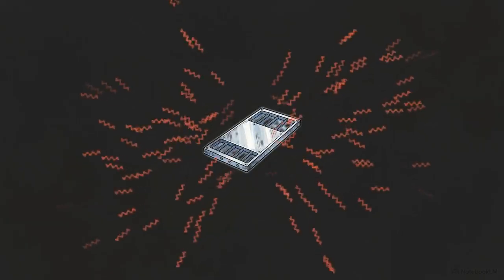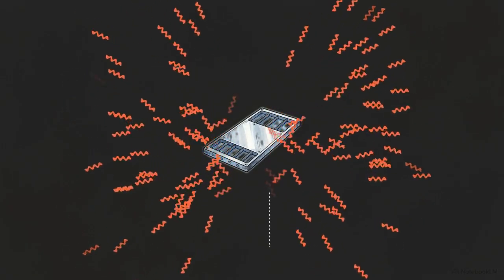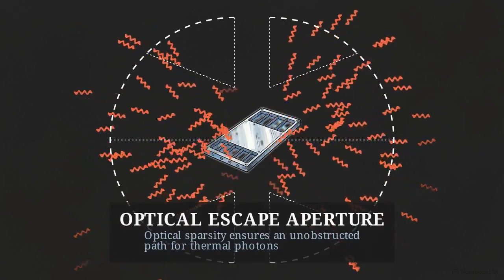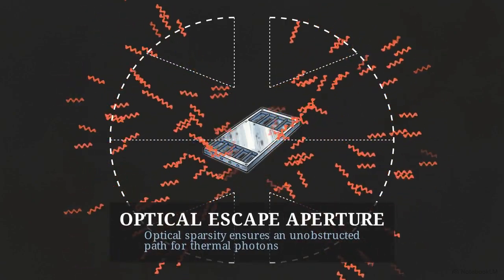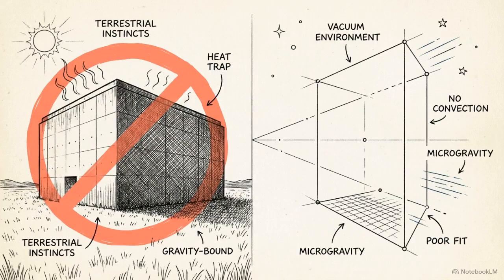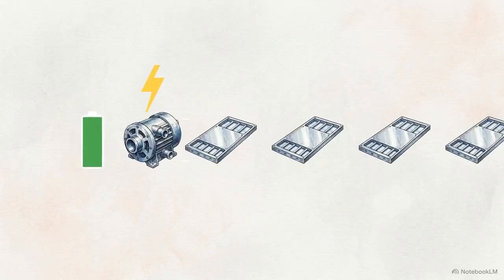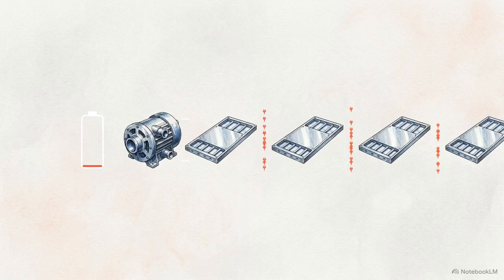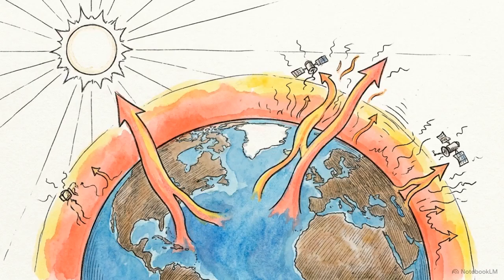Every element of this design, from its extreme operating temperature to its optical sparsity, is dictated by the physics of escaping thermal photons. Terrestrial data center instincts are a poor fit for this environment. Heat pumps add too much power load. Dense radiator packs trap their own heat, and low Earth orbit is too thermally contaminated for industrial efficiency.